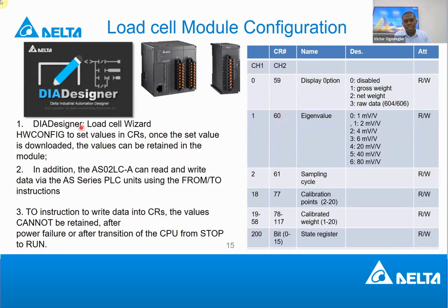Besides the TO instruction, there are also some special, important addresses you can write in DIADesigner. If you open the monitor table and set up the address, you can also write some parameters to it. If you look at this side, you can see some parameters or control registers that are very important in the load cell module. The control register is 0 for channel 1, and 59 for channel 2. If you look at this module, there are two channels: up is channel 1 and below is channel 2. Each channel has its specific control register, and you can command them to read and write using this instruction.